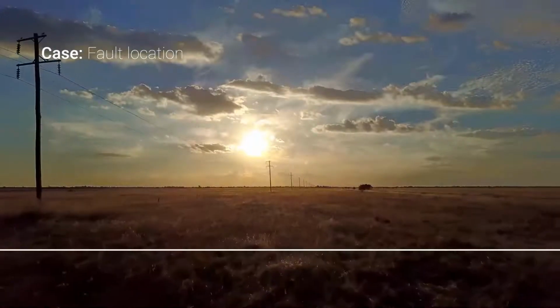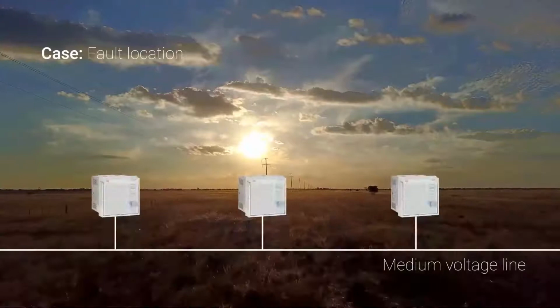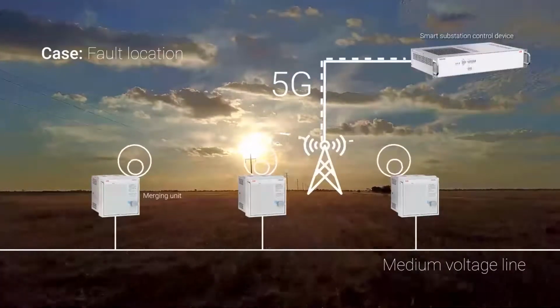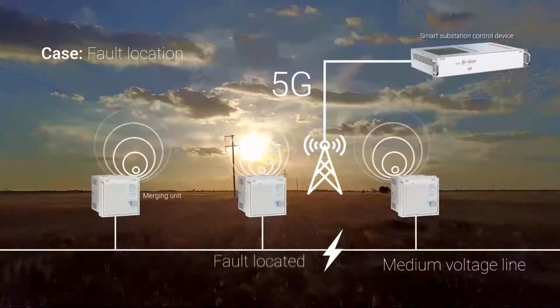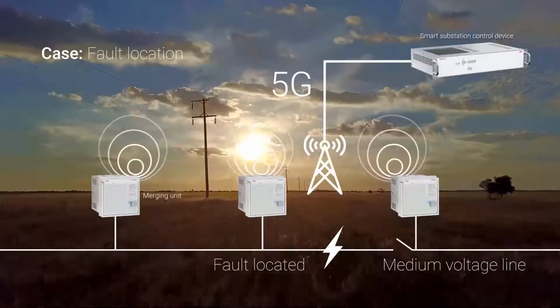With centralized fault location, the problems can be located in seconds. Cost-effective merging units along the power line publish the digitized voltage and current measurements to the centralized smart substation devices, which compute the fault location and initiate the required actions.